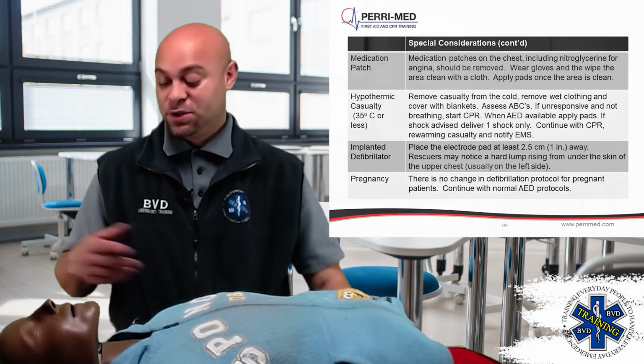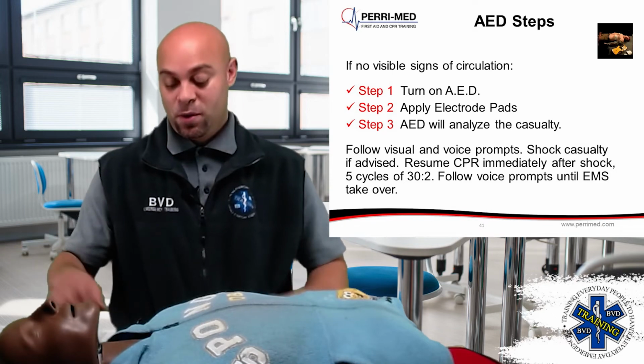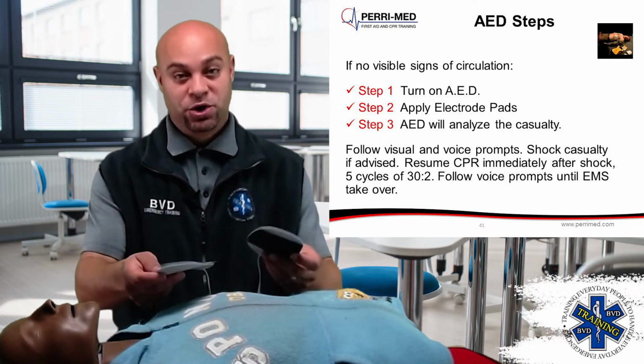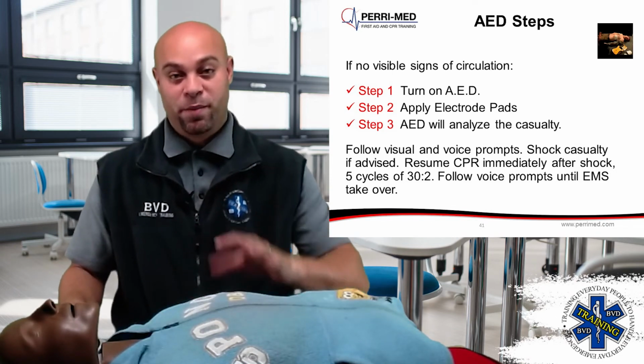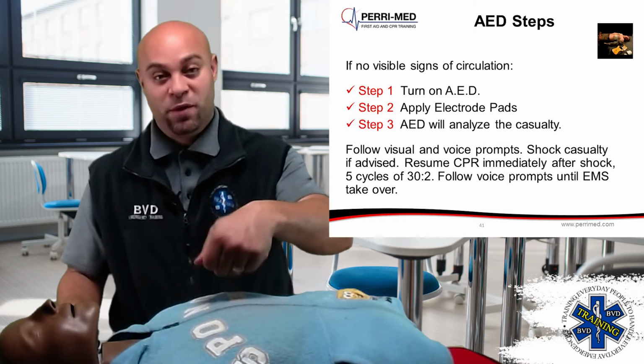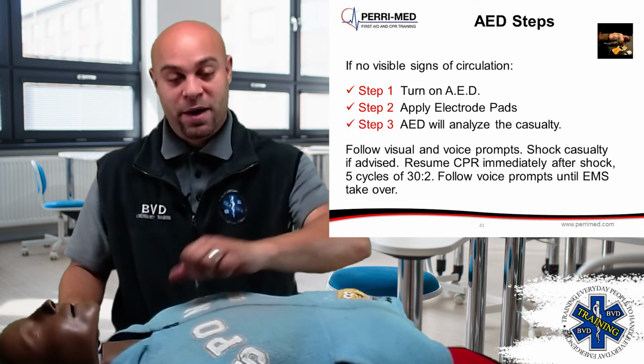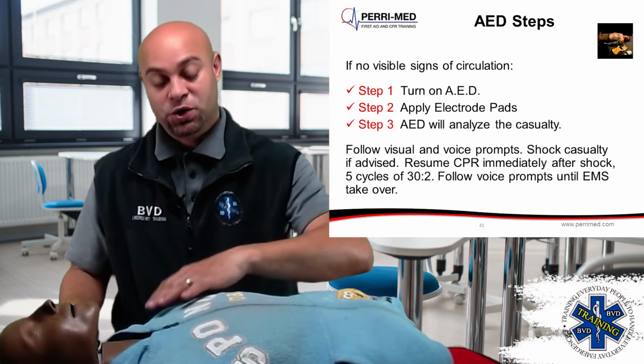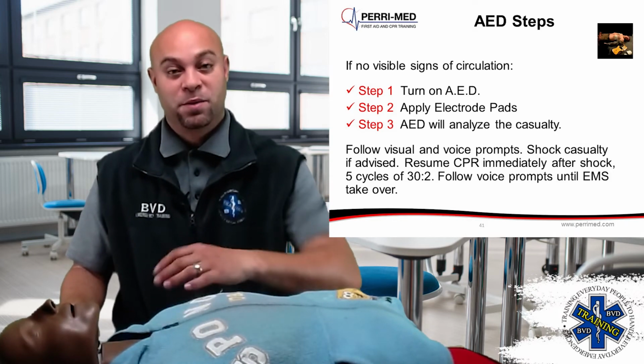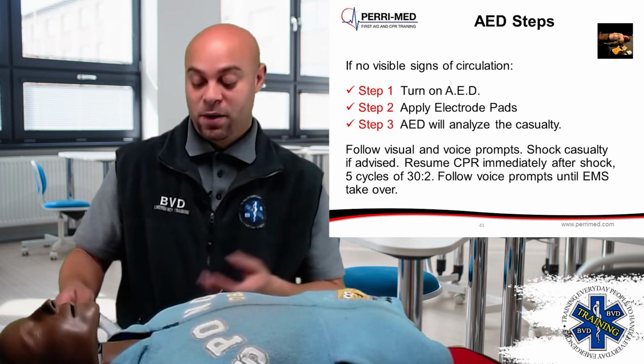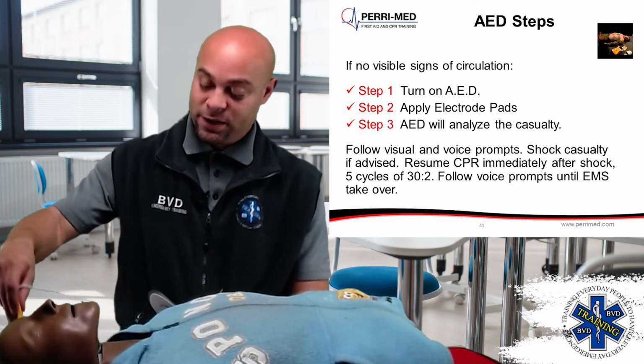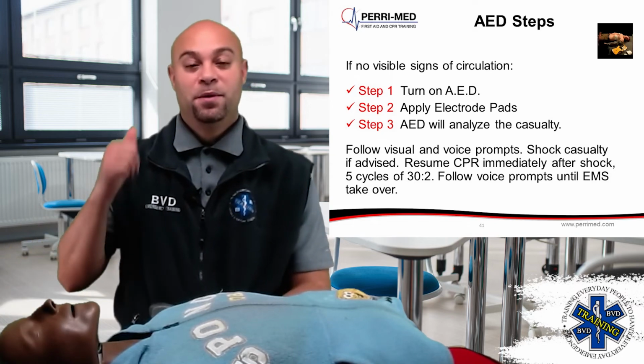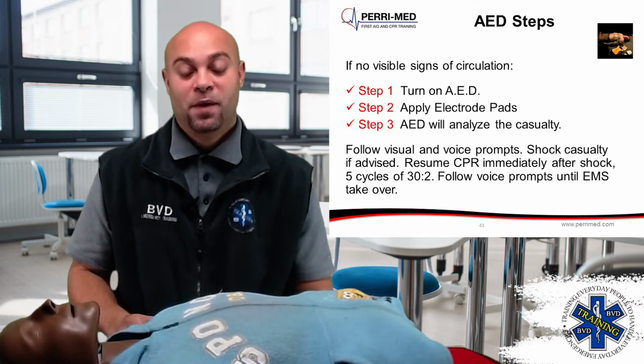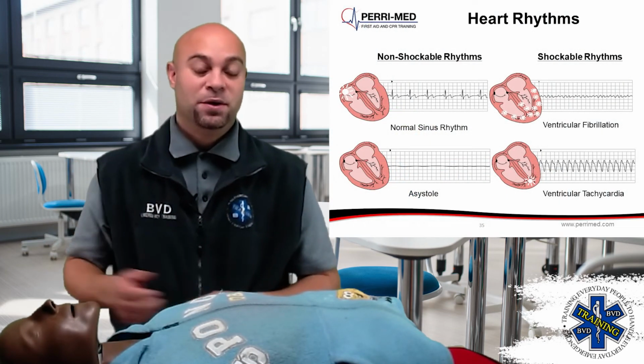Okay, so then our steps. We're going to first turn on the unit. Then we're going to put the pads on the patient's bare chest. So we need to expose the chest and put the pads in place, right? Dry shave them if we need to. Put the pads on, peel any medicine patches off, move pads an inch away if there's a pacemaker or a defibrillator that's implanted, right? And then we need to plug the pads connector in next to the flashing button, and then it will analyze. It will do all the work for you and analyze to say whether a shock is advised or not advised.